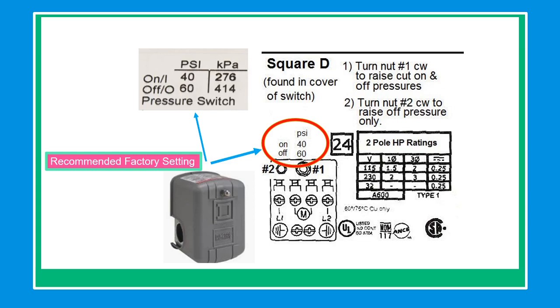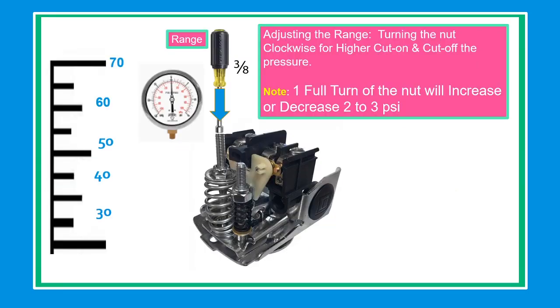By adjusting the center nut, you will lower or raise the range, so you can increase or decrease the pressure by turning clockwise and counterclockwise. Turning the nut clockwise will increase the pressure. Note: one full turn of the nut will increase or decrease the pressure by 2 to 3 psi.